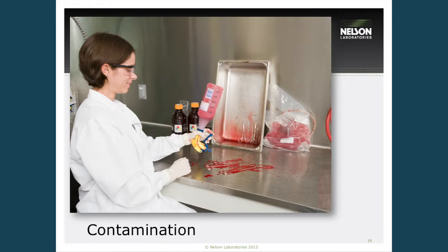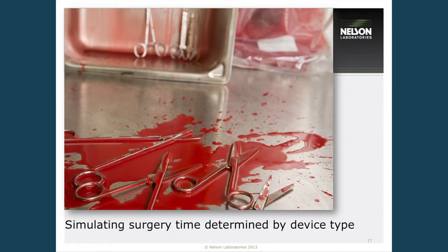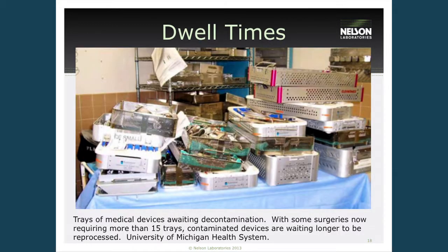And so we want to make sure that we get every kind of nook and cranny in there contaminated. We also want to actuate the devices as they would be used in the surgical setting to make sure that the blood penetrates any areas where appropriate. We always make sure the device is set in the soil for the determined amount for the surgical time. And then the dwell time.